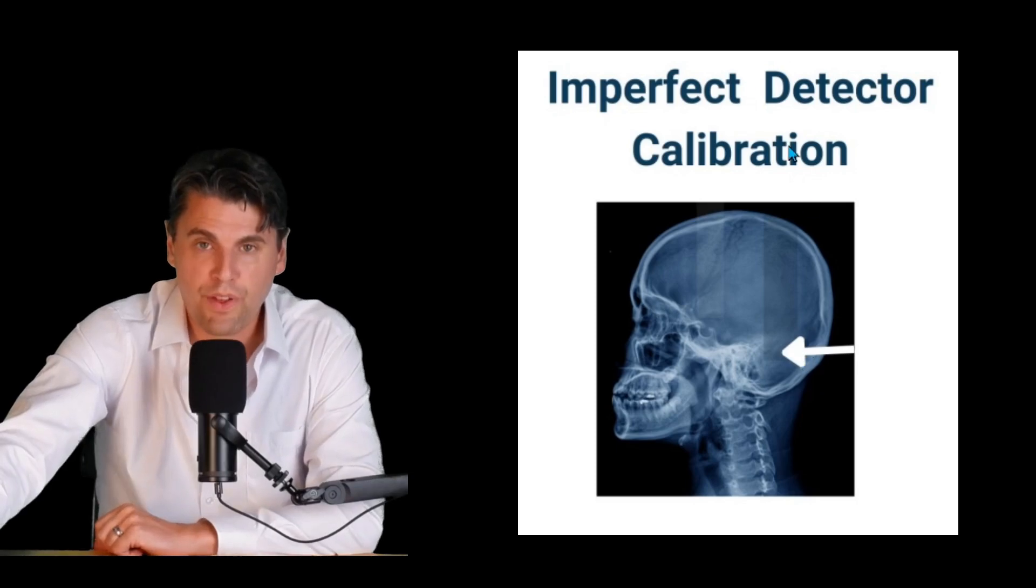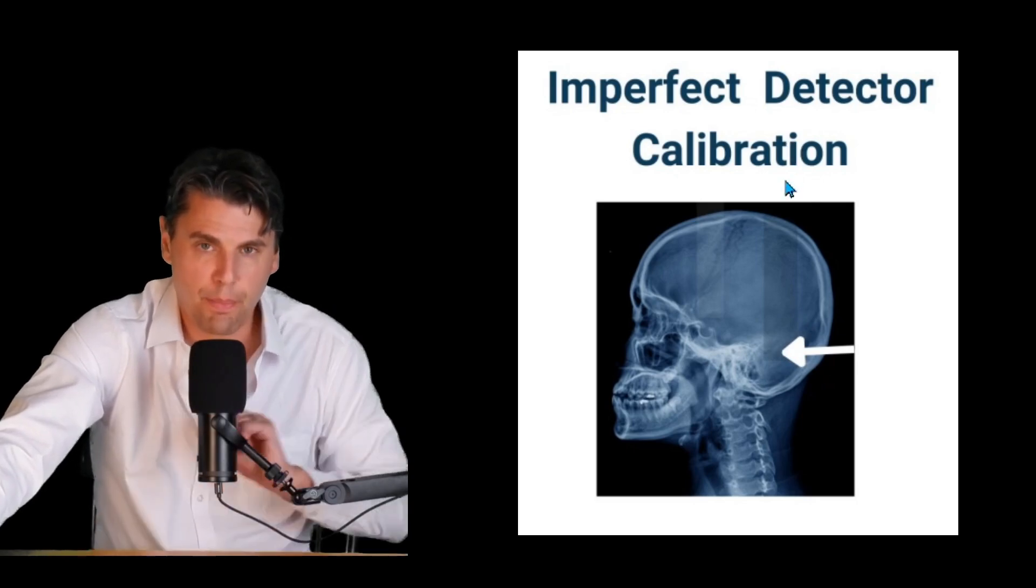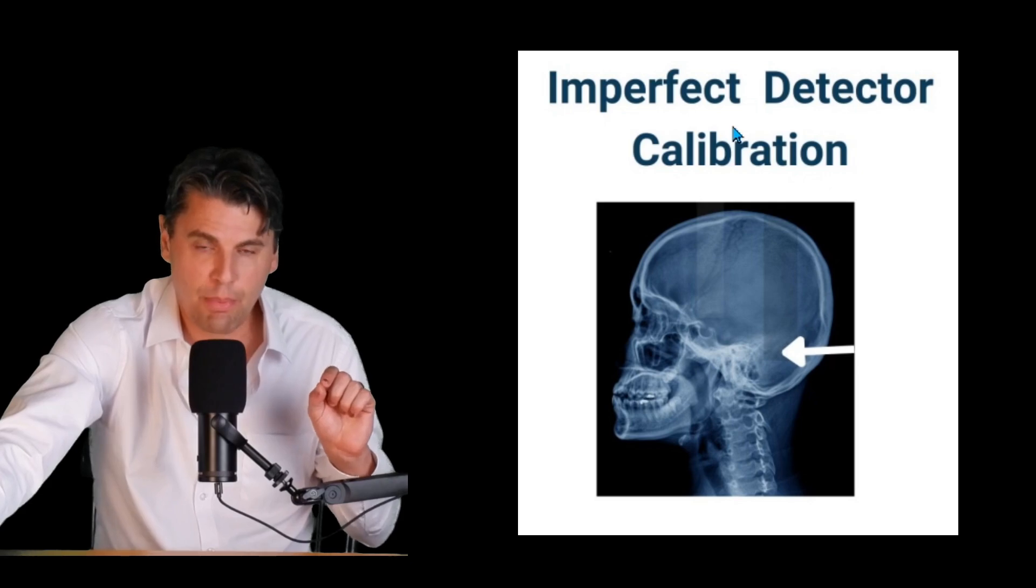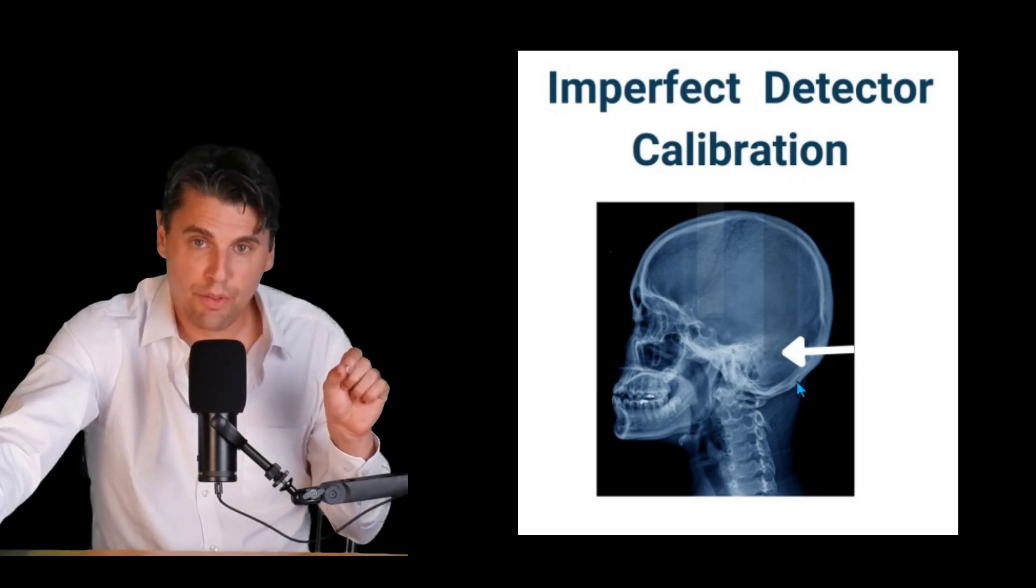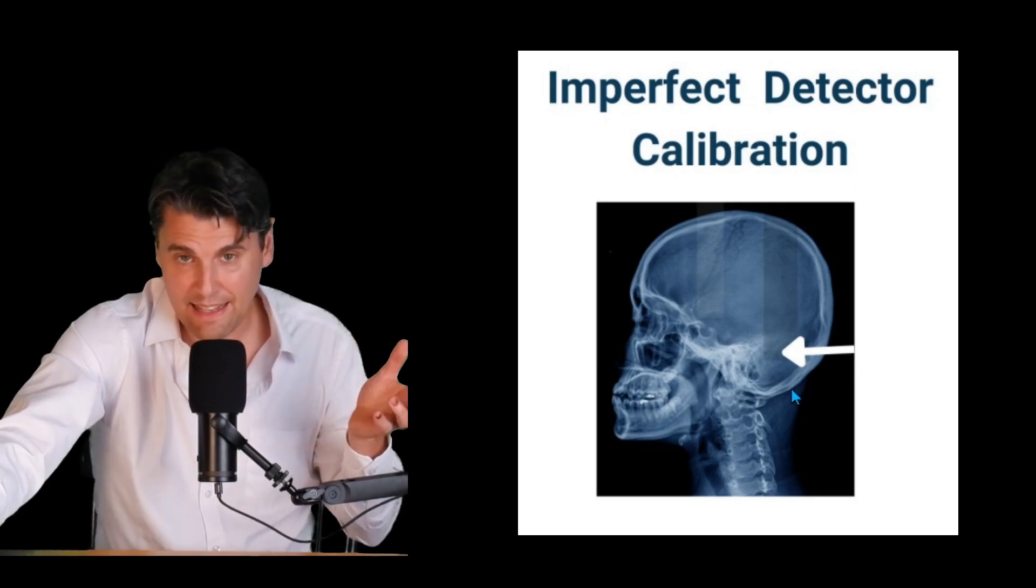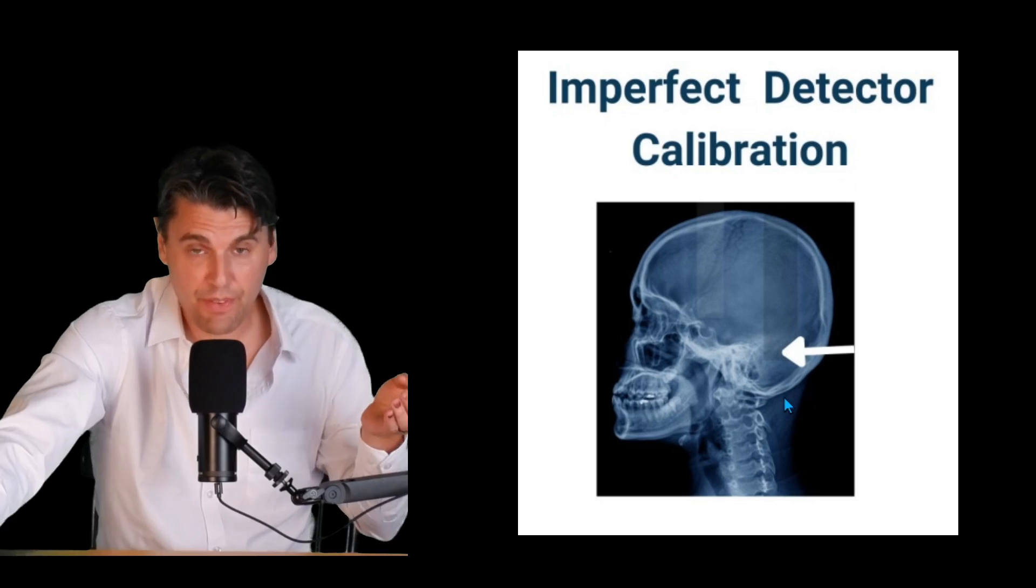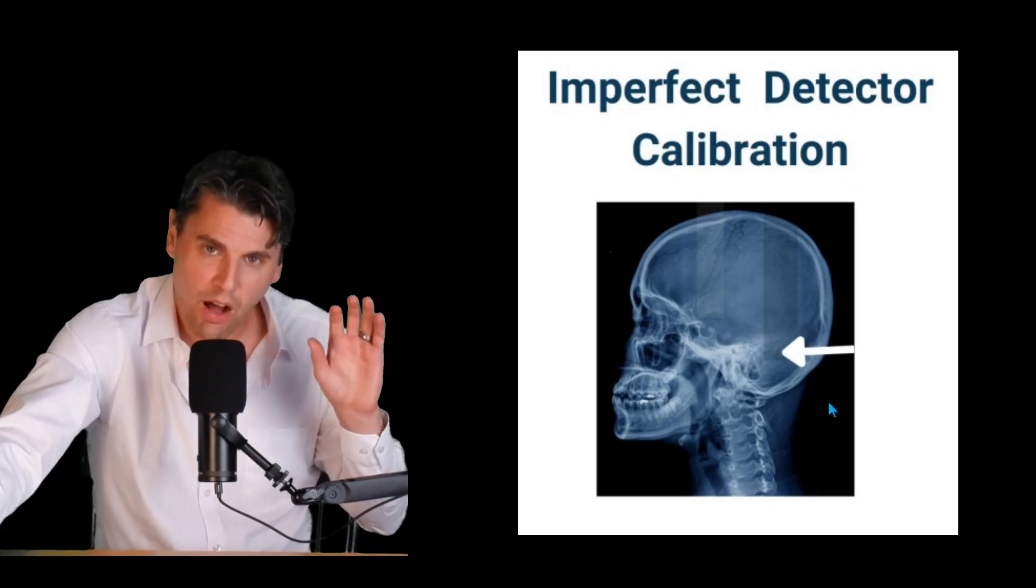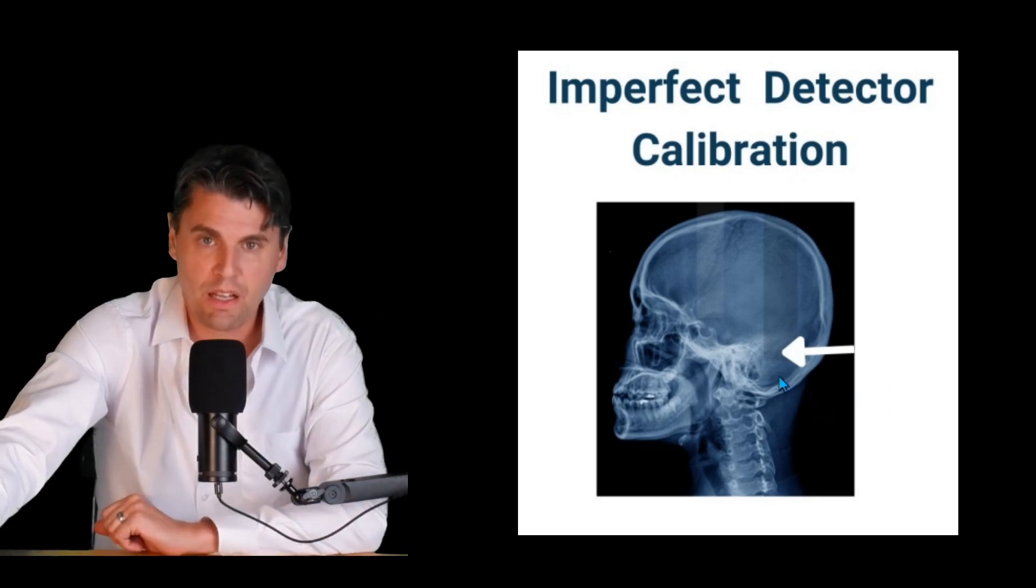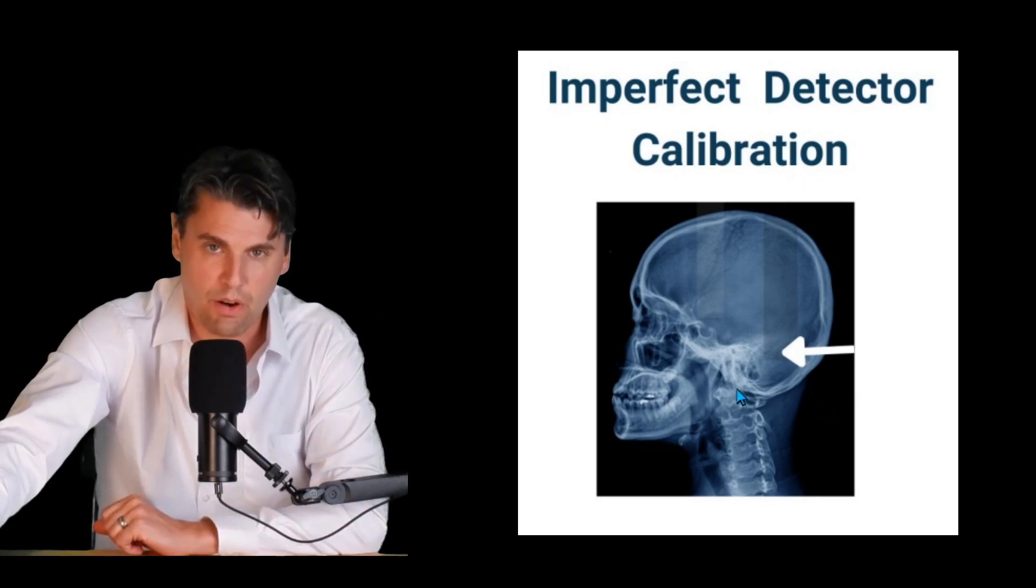It's also possible for there to be essentially strips that are a little bit different. They're showing up a strip in the image that's a little bit different because that part of the image is actually getting read out through one ASIC or one specific piece of electronics and if it is a little bit off in what we call the calibration it can look a little bit brighter or a little bit darker.